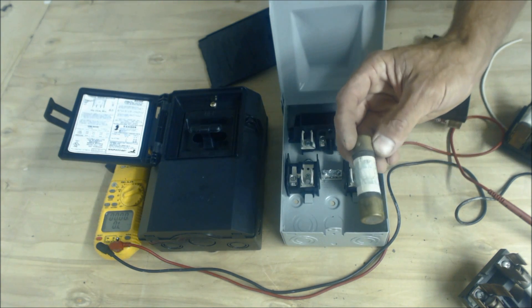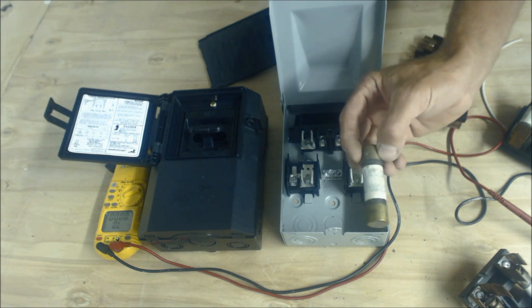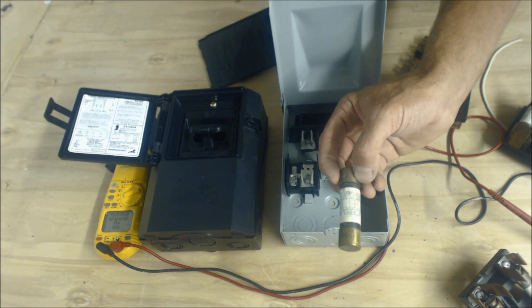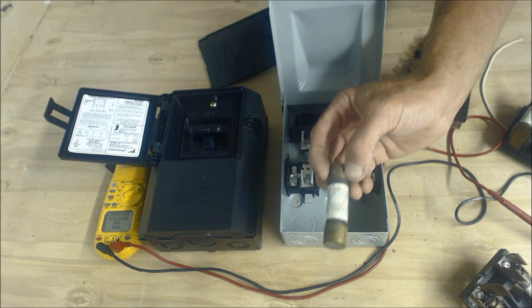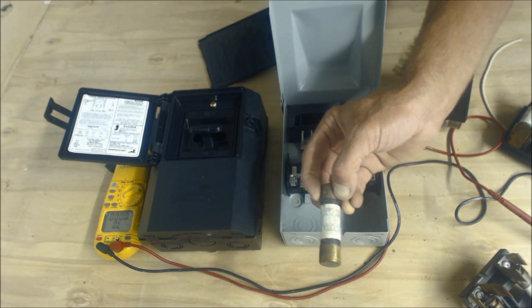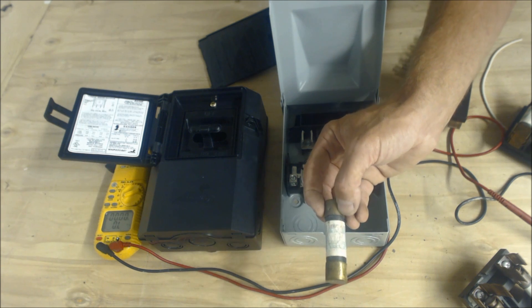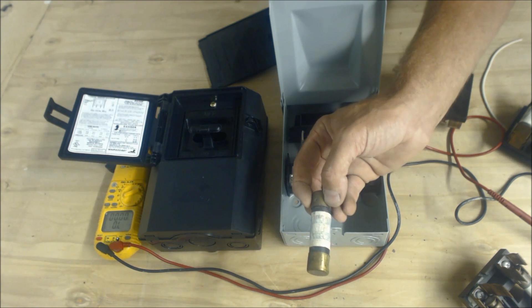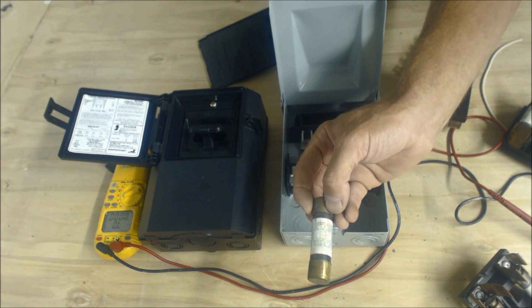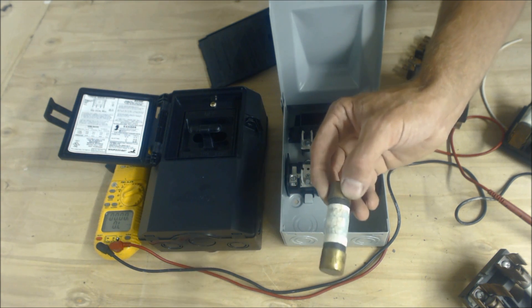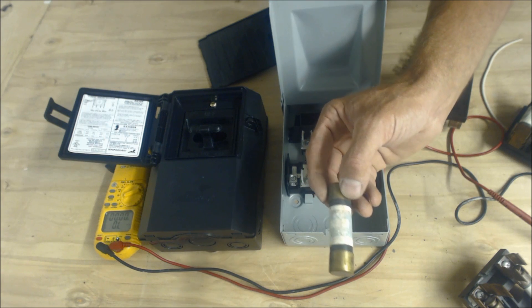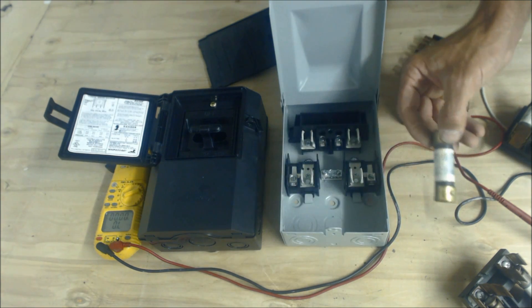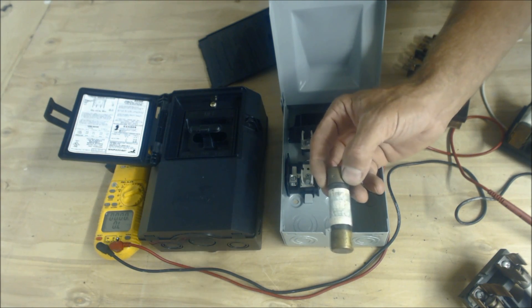I will tell you that I've gone to job sites where one of the fuses is blown. I replace the fuse, check the charge, check the amp draw, make sure the amp draw is not climbing. And actually over time, the amp draw should lessen on a unit. So say you got it running after about five minutes or so, the amperage should start reducing. Say it's from five to 15 minutes, the amperage should reduce, because what's happening is you're actually lowering the pressures in the system because you're cooling the house. So most of the time that's happening, it's only lessening a little bit, or lowering a little bit, as far as the amperage, but it's noticeable when you're reading it on the multimeter.